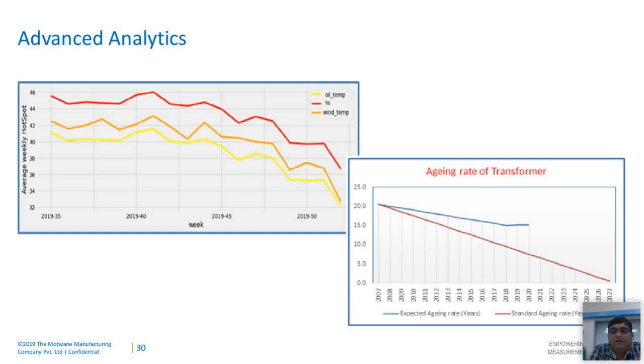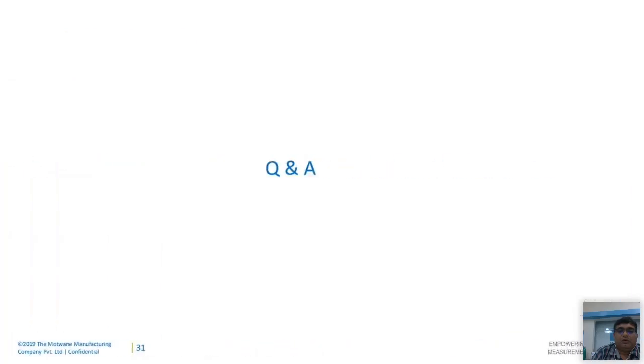Typically in case of greenfield, if you have this solution installed from day one, you get the exact rate based on the thermal modeling. However, in case of brownfield, the previous loading conditions, if monitored or recorded, can be backfilled, and we get a slightly realistic value. From the day this solution is implemented, you can actually see the actual aging rate based on the dynamic loading condition. So this was all about the monitoring part of the entire solution, which talks about digitalization of testing of the electrical asset.